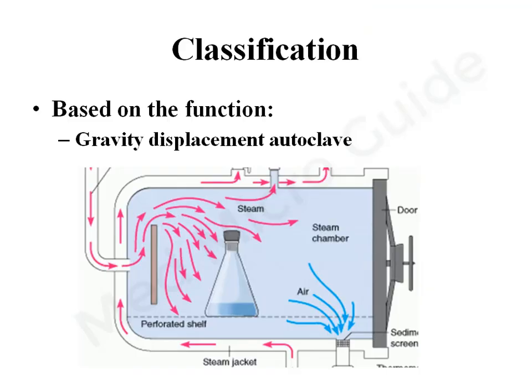There are various types of autoclaves. Based on function, we classify autoclaves into gravity displacement autoclave, high-speed pre-vacuum autoclave, steam flush pressure pulsing autoclave, and portable steam sterilizers.